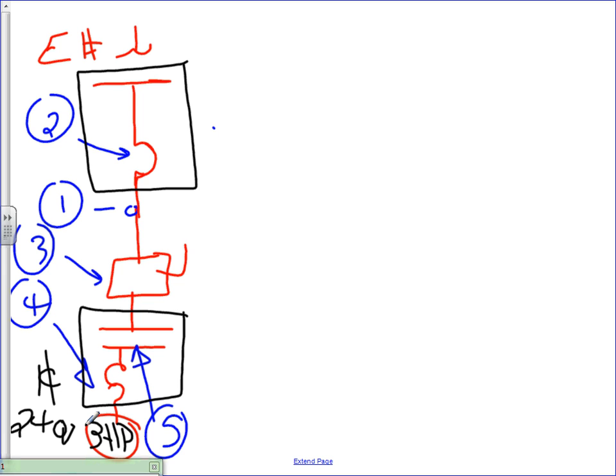Now, before we start, we're going to assume, because it's a sump pump, we're going to be using conduit and wire. We're using conduit wire, not NM cable. We're not using NM cable. Okay, so the first thing, I'm going to start right in here.